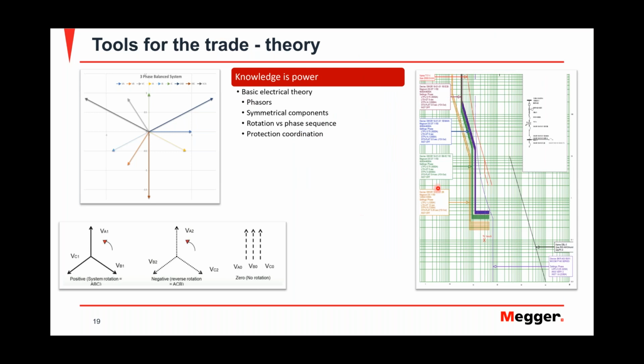You don't have to be a protection engineer, but I think it helps if, as you progress in your career, you have some understanding of protection coordination and looking at time current curves. Understand that this is a cable damage curve, this is a transformer damage curve, and this is how a 50/51 looks. If your spider senses come in when you're testing a relay and it's like, "This is not making sense. What did the engineer intend to do?", having this practical knowledge, you don't have to know the theory behind it, but knowing how this works, you could see in a graphical way the intent of the engineer.